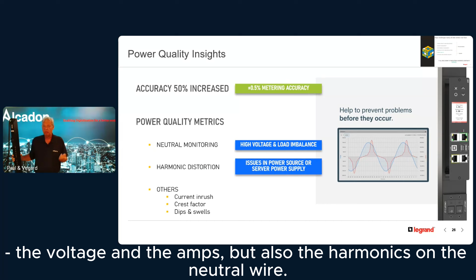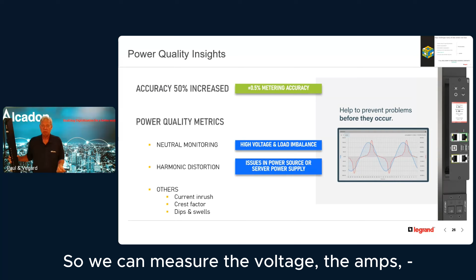Then we have started measuring the power consumption, the voltage and the amps, but also the harmonics on the neutral wire, specifically on 3-phase power distribution. It's very important to monitor the neutral wire, because the neutral wire normally in a data center is not protected. You are protecting your phase wires, but you're not protecting your neutral wires. So there can be a dangerous load on a neutral wire, causing a serious problem in the data center. So we can measure the voltage, the amps, but also the harmonics going over this neutral wire.